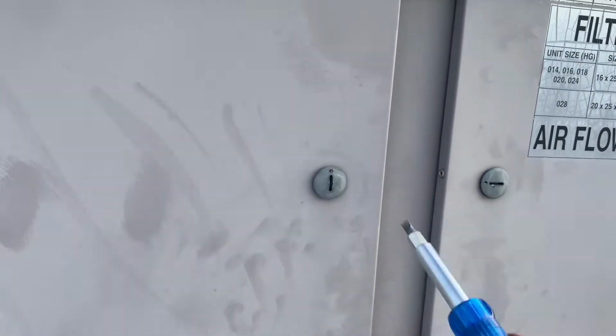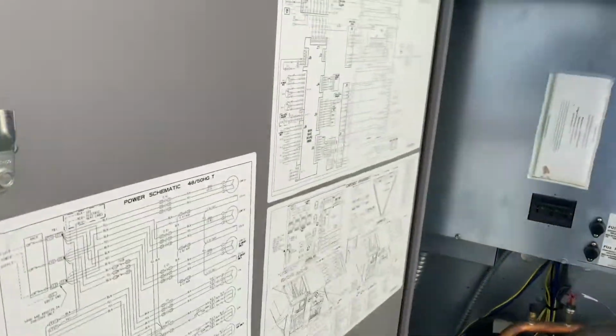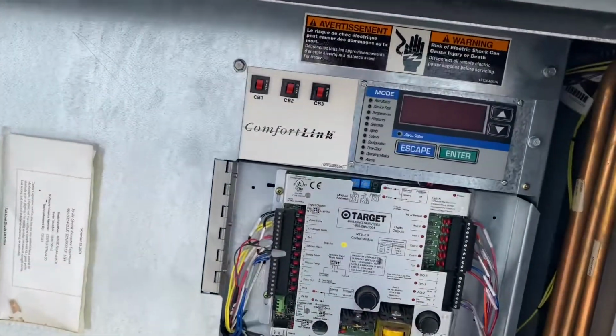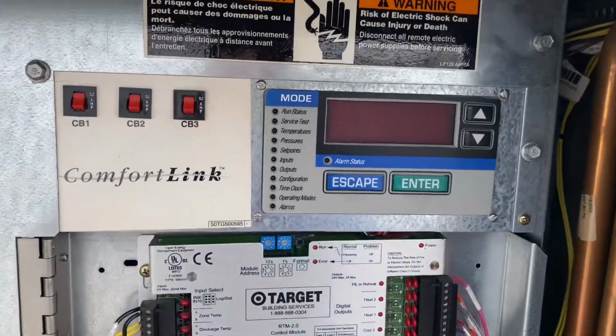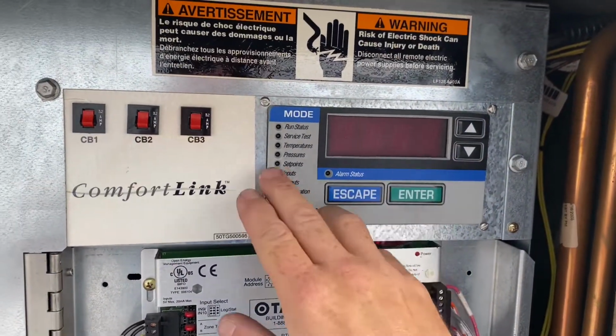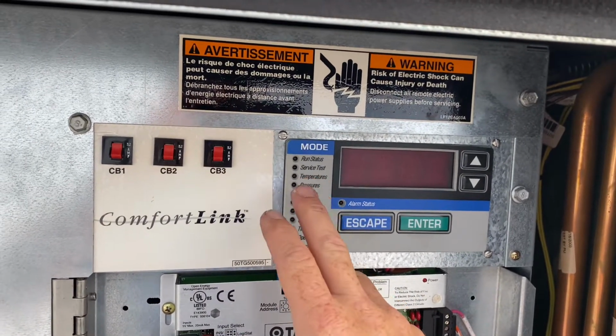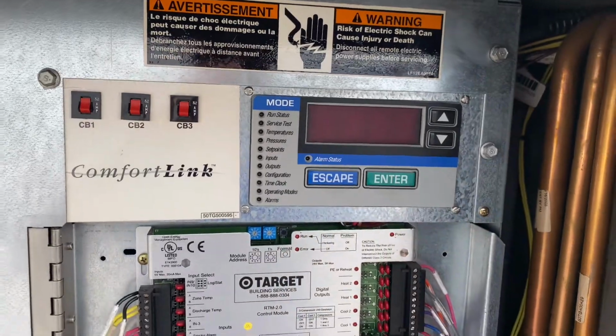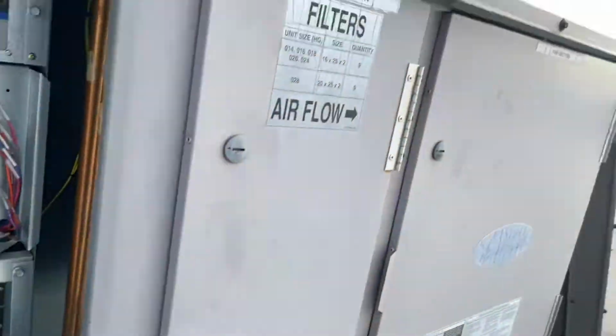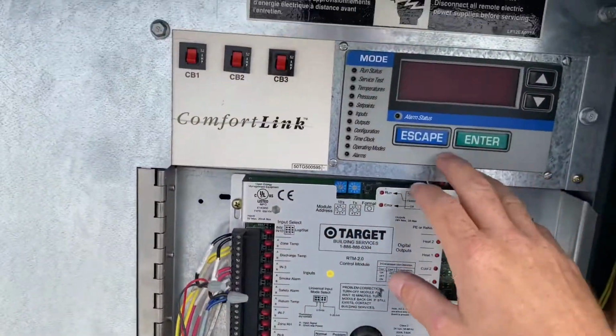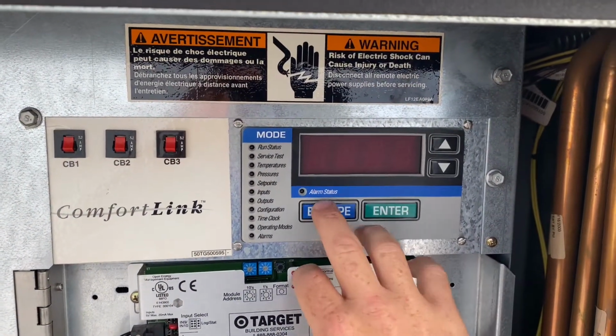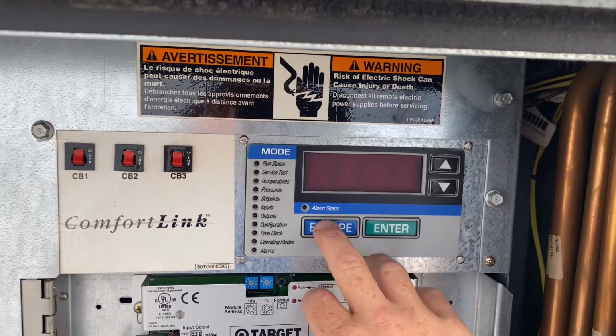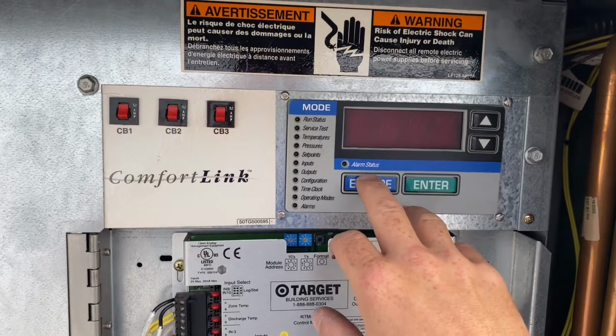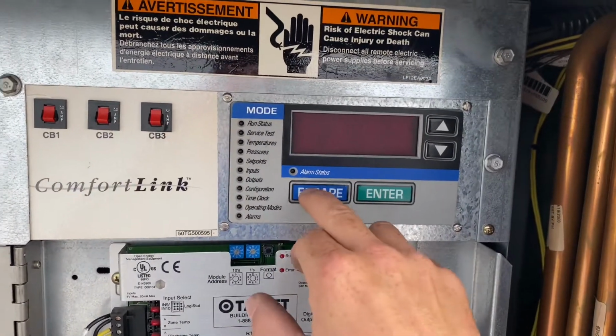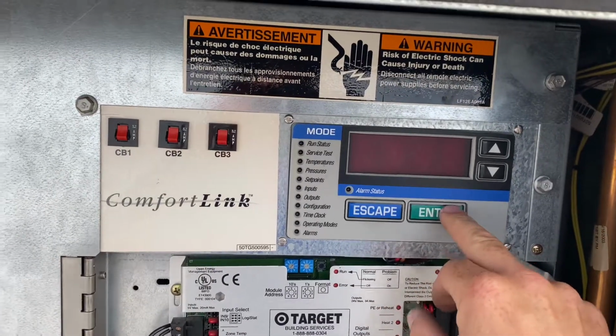First, undo these door locks. Get this unit open. Let's see if we can tell anything right off the bat. Okay, right off the bat, these Carrier units have these main controllers where you're able to put it in test mode and see different temperature set points as well as the temperatures it's running at, and be able to test all the individual parts: compressors, condenser fans, blower fans, and whatnot. But anywho, back to the simplistic part of it anyway, as far as seeing right off the bat what's going or not going on. And no power on the board, not doing anything whatsoever.